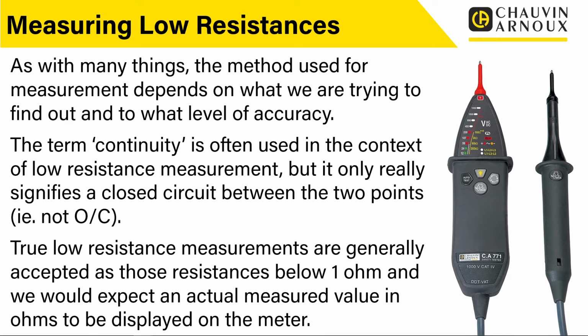What are we trying to measure? What are we trying to prove? Like I say, if we're just trying to trace a cable by beeping both ends of a connector, yeah, perfectly acceptable to use a continuity checker with a beep function on it. But when we actually want to measure the quality of connections, maybe on a busbar, or check that a relay is working properly, we really need to get right down into those resistances, and that's where true low resistance measurement comes in.